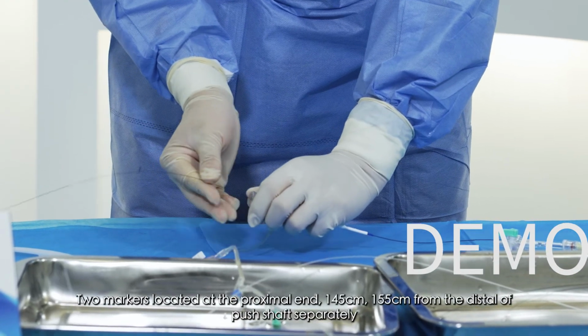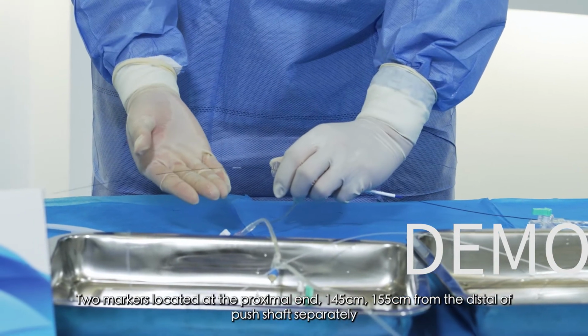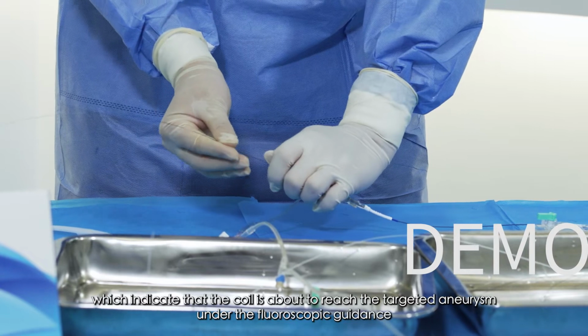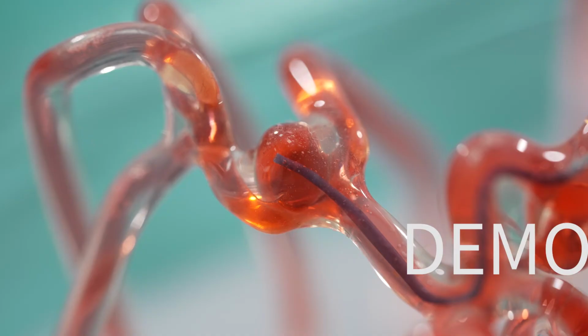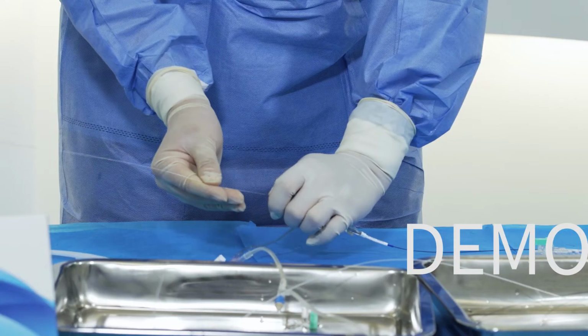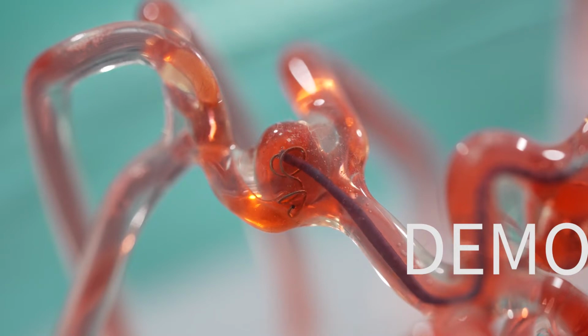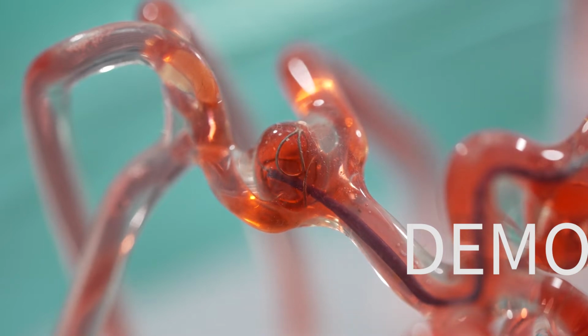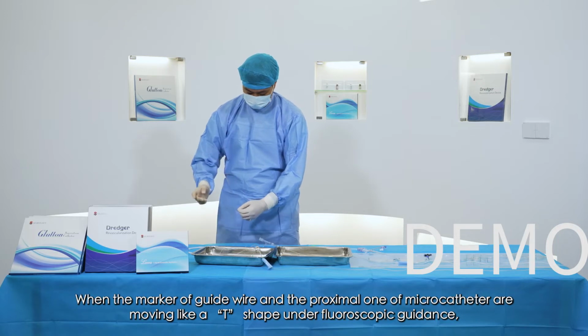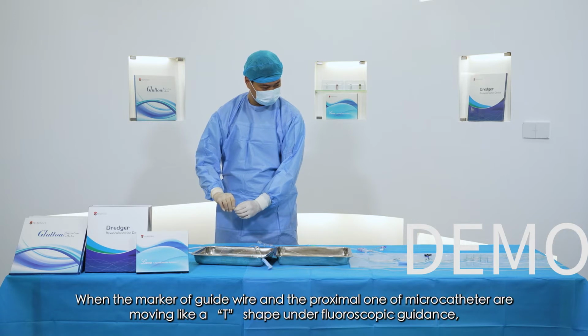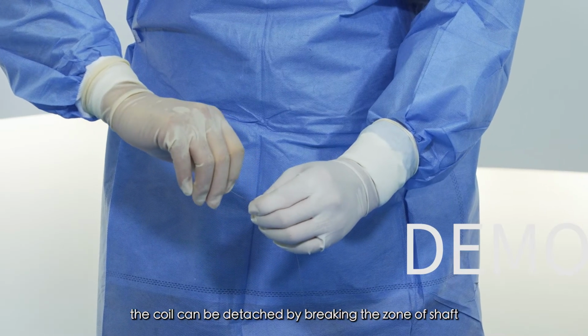Two markers located at the proximal end, 145 centimeters and 155 centimeters from the distal end of the push shaft respectively, indicate that the coil is about to reach the targeted aneurysm under fluoroscopic guidance. If the coil does not frame well, it can be withdrawn and then released again. When the marker of the guide wire and the proximal one of the microcatheter are moving like a T-shape under fluoroscopic guidance, the coil can be detached by breaking the zone of the shaft.